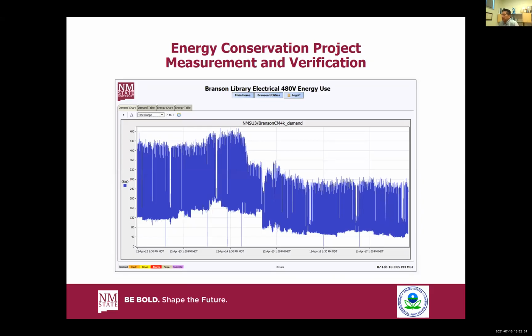Part of what's really helped us in developing our smart metering is, as we implement energy conservation measures on campus—that could be LED lighting conversions, or more efficient HVAC systems—the project design says it should perform at this level, and therefore reduce energy, reduce your carbon footprint, save money, and so on. But if you can't validate that, if you're only looking at the monthly bill and scratching your head as to why it's not going down, you can't really analyze or assess what we call measurement and verification—whether what you did is actually performing as designed. And if it starts to deviate, it allows you to proactively initiate corrective action instead of having it run out of sight, out of mind, sometimes for weeks or months before you realize there's a problem.